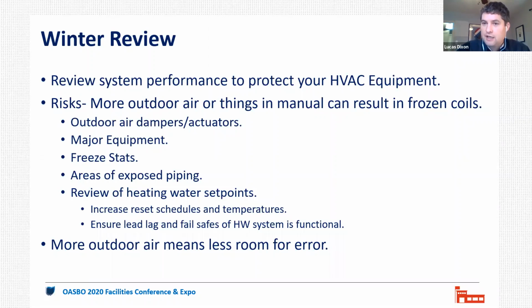Anything else on a good winter review, Matt? Things like damper seals, placement, freeze stat placement. Are your sensors, things like mixed air sensors, placed correctly to actually give you a good idea of what the mixed air temperature is doing? Those sort of things. Yeah, good point. Getting your eyes on your freeze stat, make sure that the sensor has not come detached from the coil and fallen down at the bottom of the unit. Right. Yeah. Looking to make sure you don't have one.